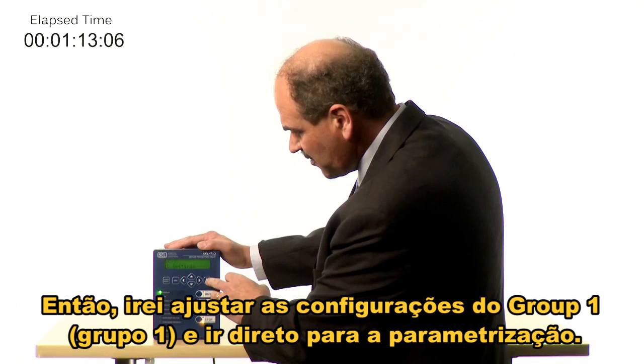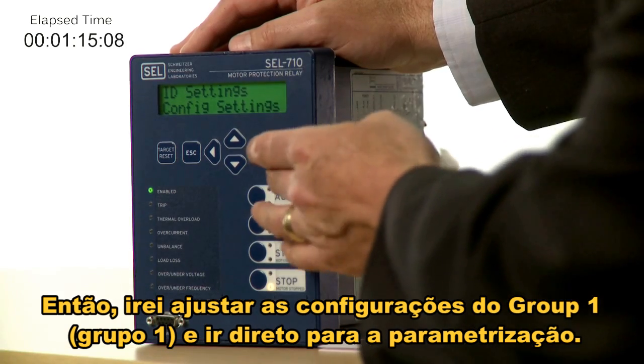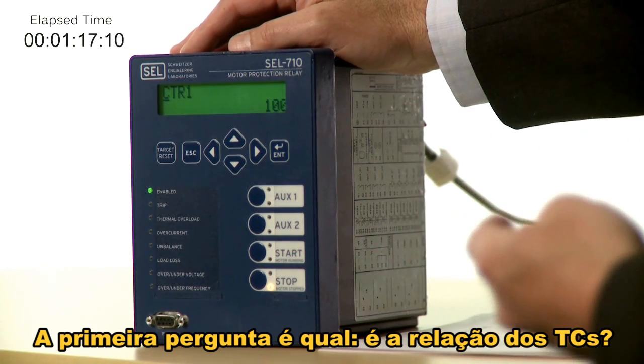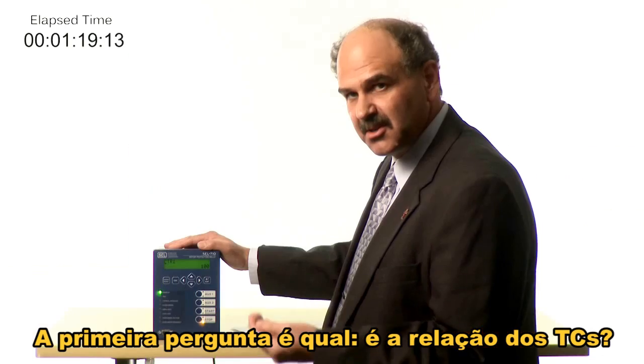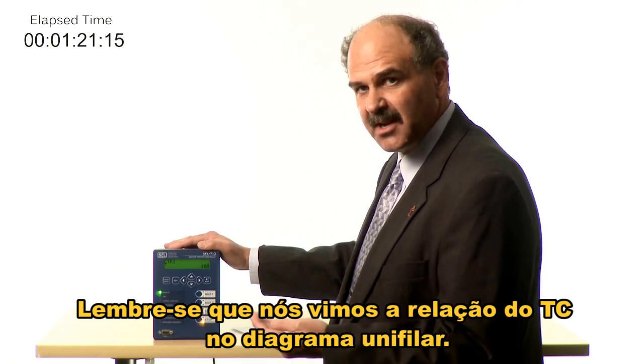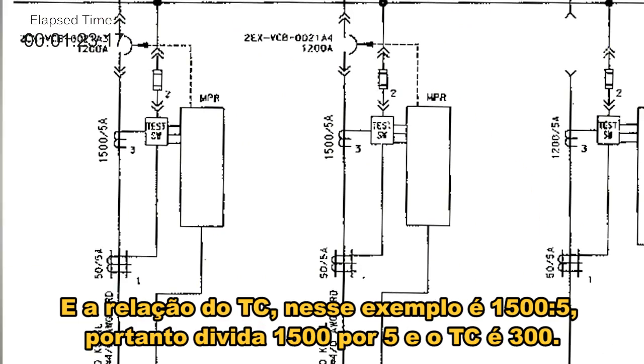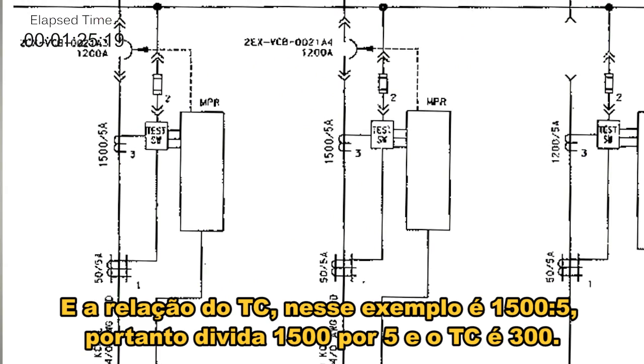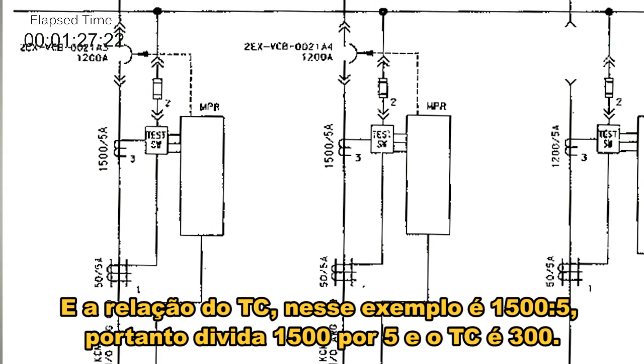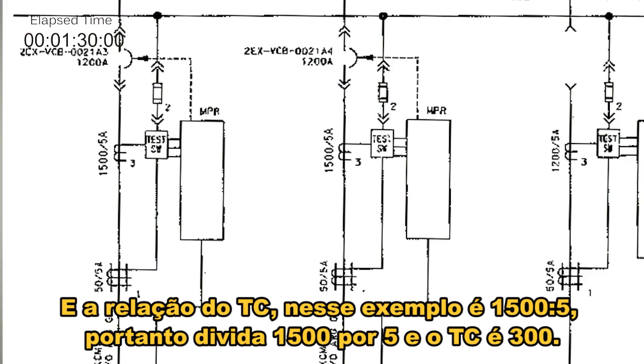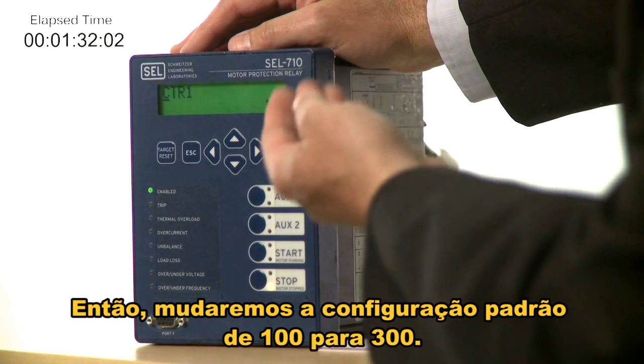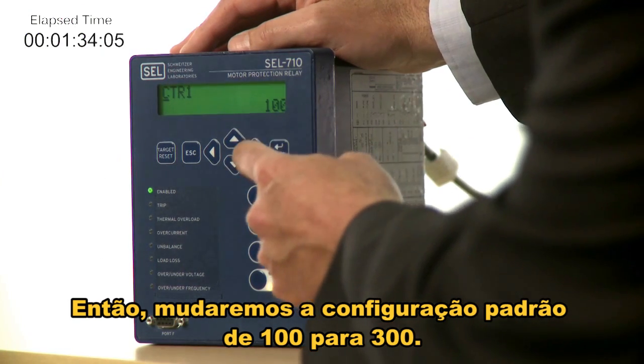So I'm going to set my Group 1 settings and go straight to the configuration. The first question it asks for is what's the CT ratio? You remember we pulled the CT ratio off the one-line diagram. In this example, it's a 1500 to 5 CT, so I divide 1500 by 5 and I end up with my CT ratio of 300. So we're going to change the default setting from 100 to 300.